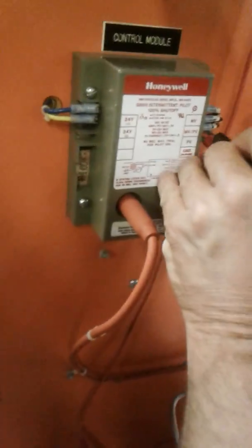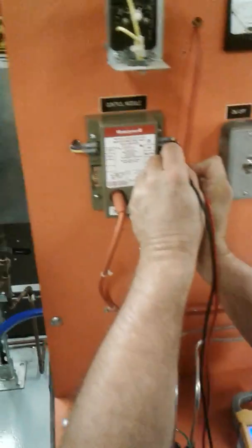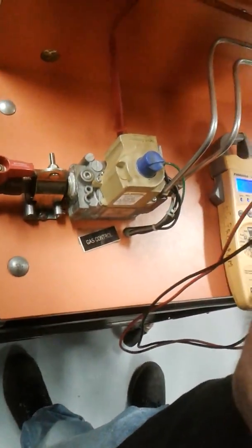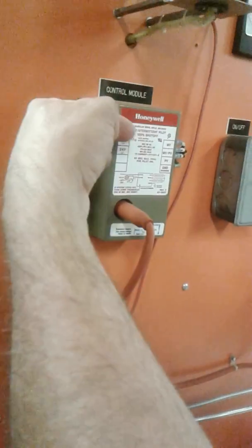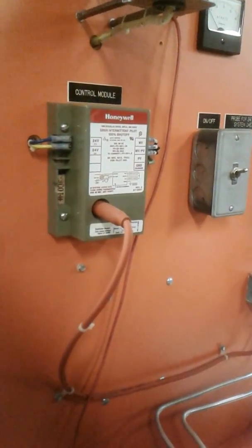I need to work my way backwards, okay? So, we're gonna follow the wires up. Let's see if we got voltage up here at the control module. MVPV. What do I got there, Andrew? What's that meter saying? It says 0.19. That's nothing, right? That means there's nothing there, okay? So the power is being fed into the control module, and goes down to power up our gas valve.